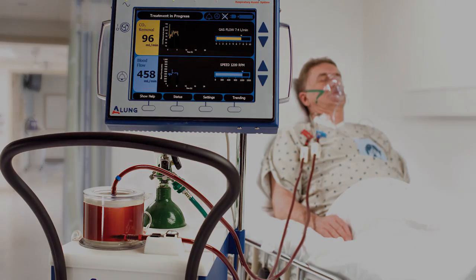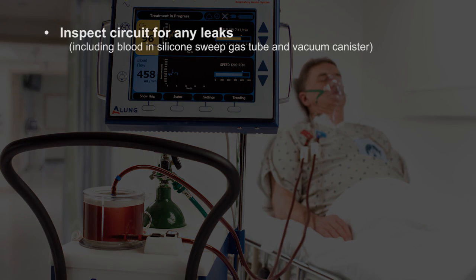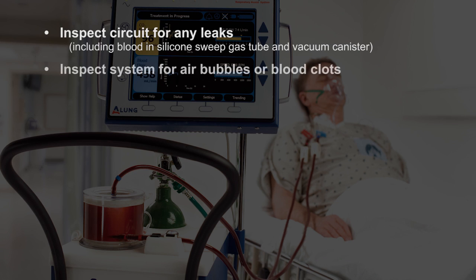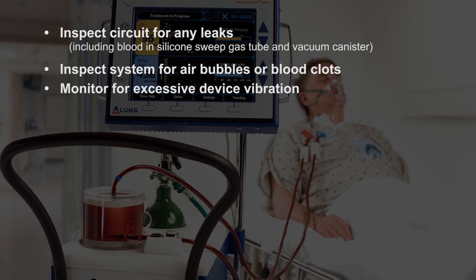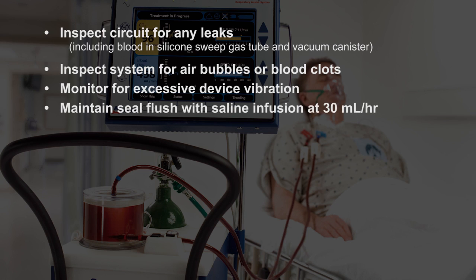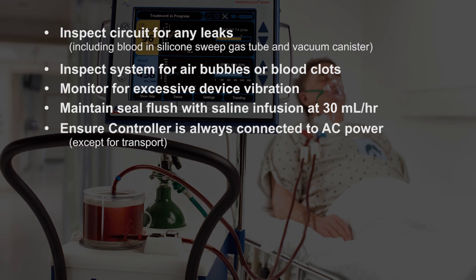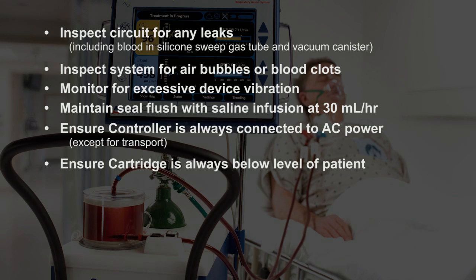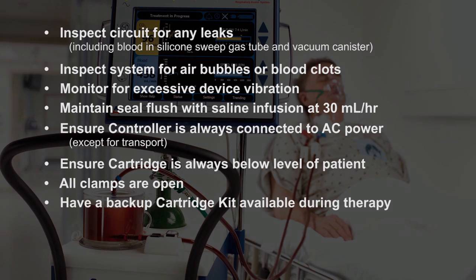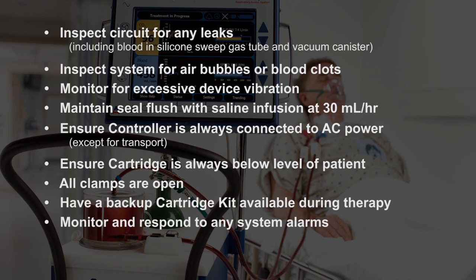Routinely inspect the system during therapy. Inspect the circuit for any leaks, including blood, silicone sweep gas tube, and vacuum canister. Inspect the system for air bubbles or blood clots. Monitor for excessive device vibration. Maintain seal flush with saline infusion at 30 milliliters per hour. Ensure the controller is always connected to AC power except for transport. Ensure the cartridge is always below the level of the patient. Ensure all clamps are open. Have a backup cartridge kit available during therapy. Monitor and respond to any system alarms. Ensure correct sweep gas is used.